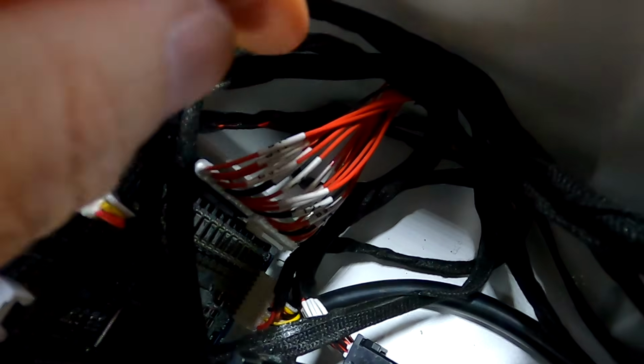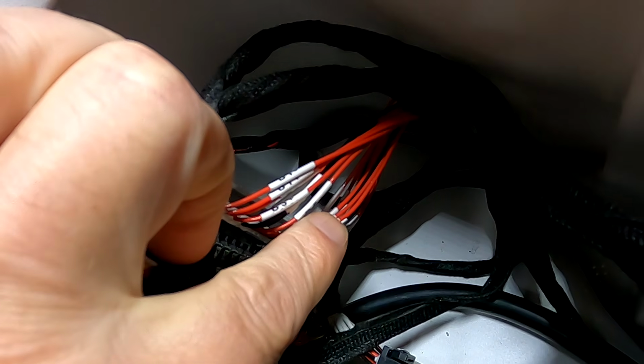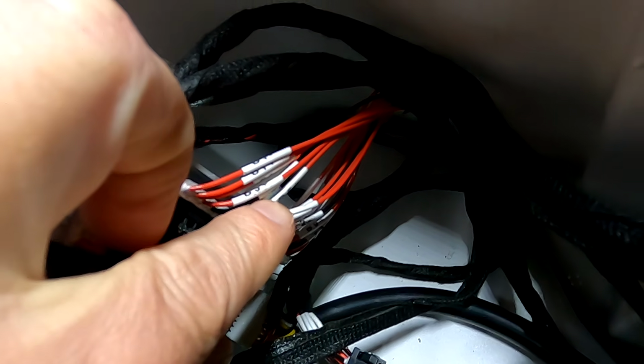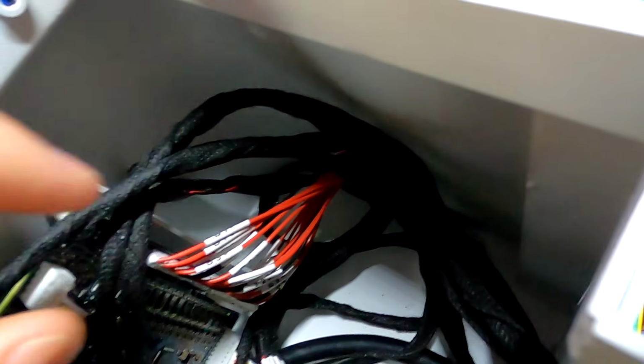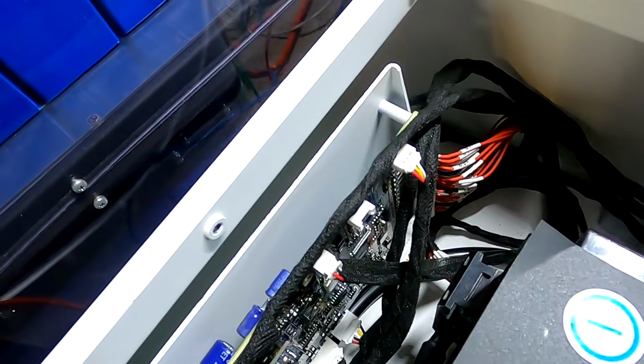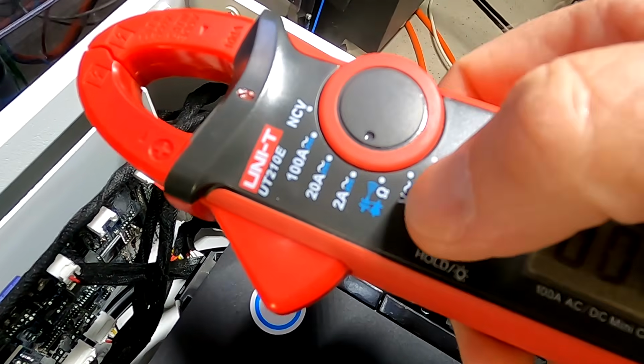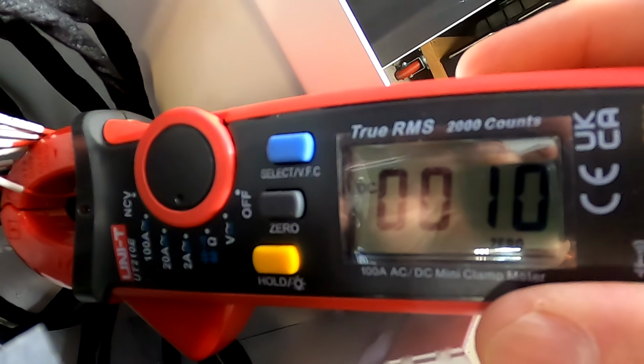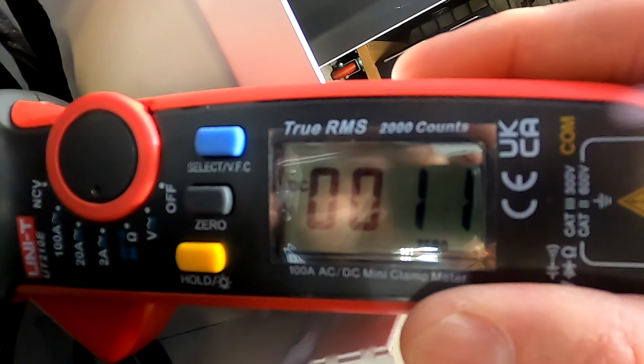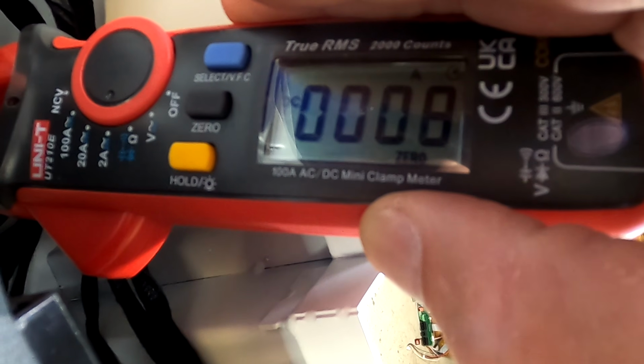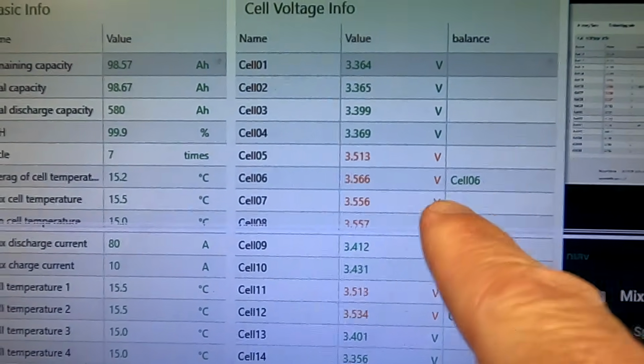I figured this cable here is our balance cable number 6. This is number 5, this is number 6 - it's a bit hard to get on camera, but they have labels actually. Let's see if we can grab this one. We set this to 2 amps. Okay, got it - number 6, and we can see a balance current here, that's milliamps - 10 milliamps. There you can see it, it's about 10 milliamps for cell number 6, and cell number 6 is what we are balancing. It's 10 milliamps.